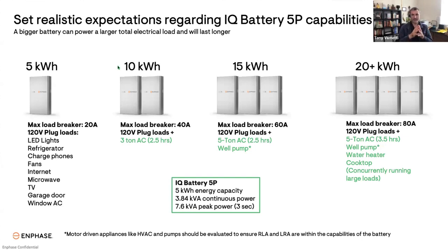So if you have 2 5Ps, that's the second one here, 10 kilowatt hours, that can start pretty much anything that is connected to a 40 amp 2-pole breaker in that backup panel. And of course, any 120 volt loads as well. An example of a very typical load that would be on a 40 amp breaker would be a 3-ton air conditioner. Now, if you've got a 60 amp breaker, say for a 5-ton air conditioner, that customer would need 15 kilowatt hours, or 3 of the 5Ps.